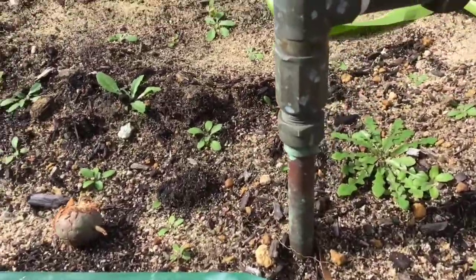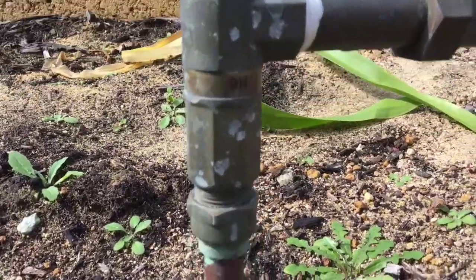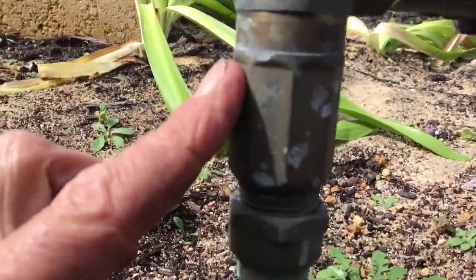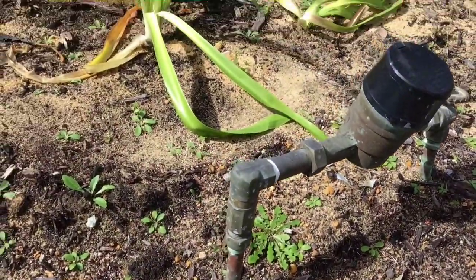I'll show you the water meter so you can see what I'm talking about - what they look like. I've done a video to show what the AVG pressure relief valves look like. This is the AVG ones. They've got a flat top and a bit of a circle on it, and usually they've got a stamp saying 500 kPa. They've got an arrow just here. So you'd assume that it'd be protected because it's got one of these, but they've failed.